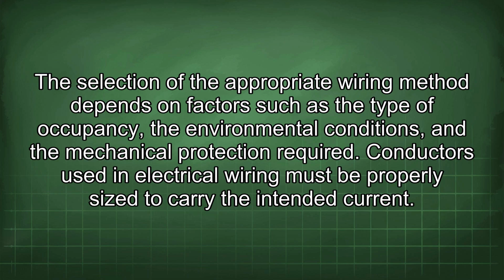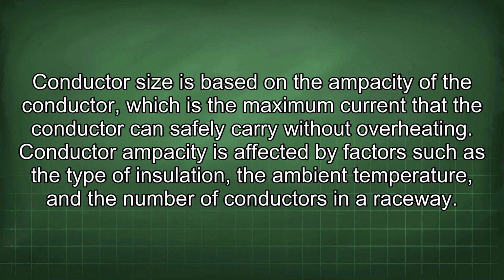Conductors used in electrical wiring must be properly sized to carry the intended current. Conductor size is based on the ampacity of the conductor, which is the maximum current that the conductor can safely carry without overheating. Conductor ampacity is affected by factors such as the type of insulation, the ambient temperature, and the number of conductors in a raceway.